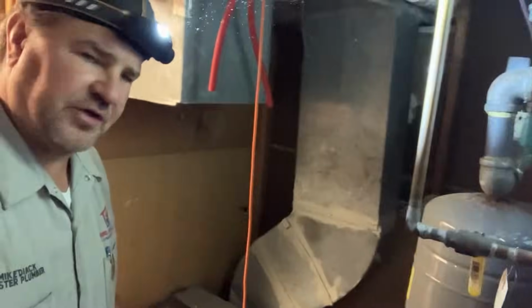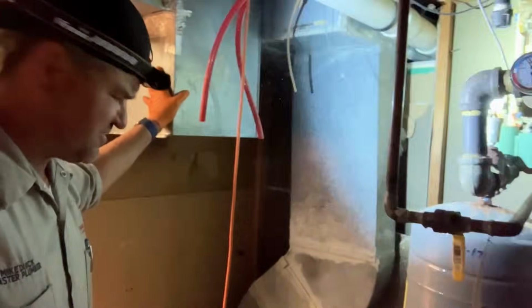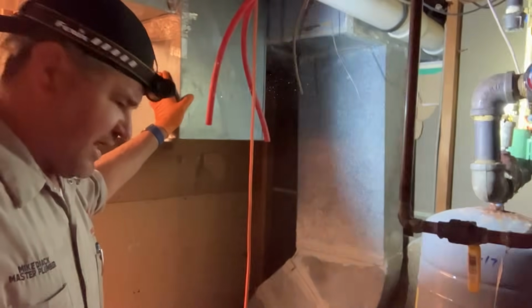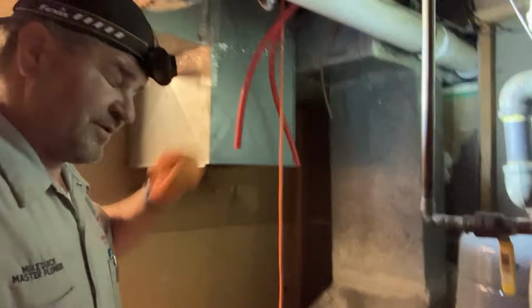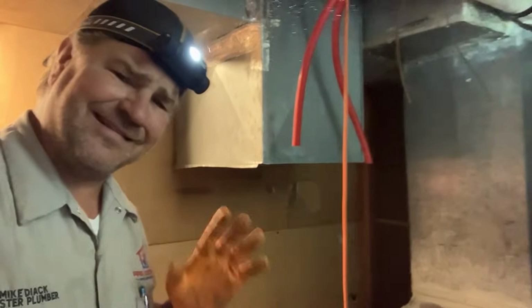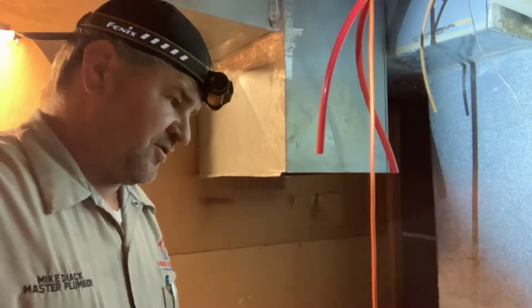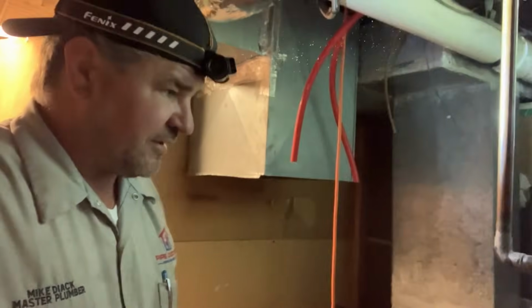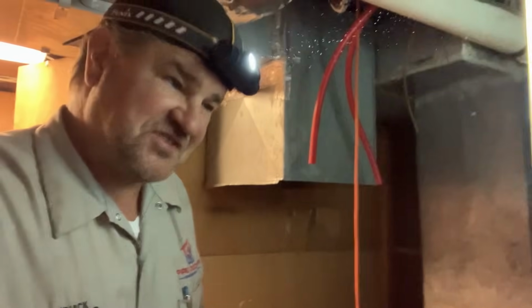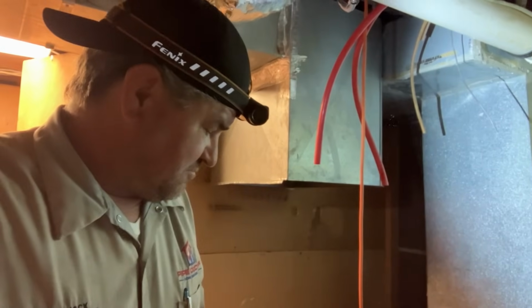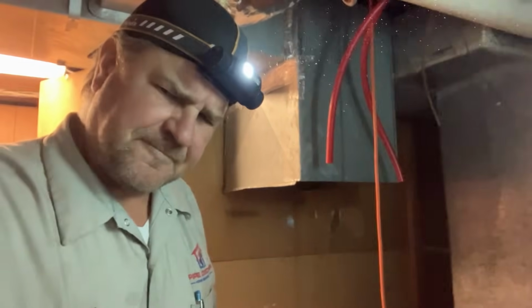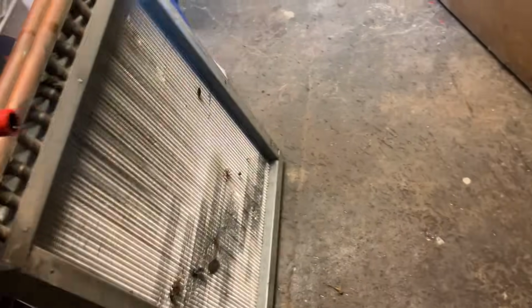All right, ladies and gentlemen, the air handler coil is removed from the supply and return plenums. I've seen a lot of crazy stuff over the course of my professional career here, but I have never seen such stupidity before like this. Check this out. I was able to pull the hydro coil, and yeah, there's a good amount of dirt there. It's going to affect airflow, and I'll tell you a story about that in a minute.